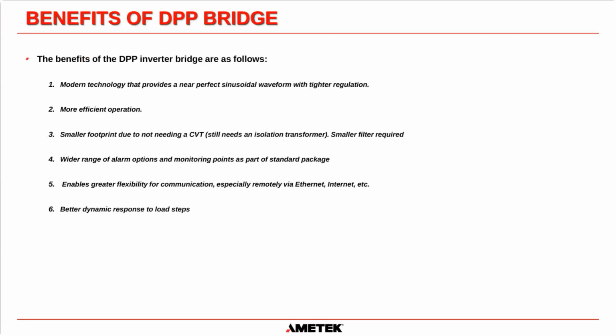One of the benefits of the DPP, the pulse width modulated inverter. Well, first of all, it's modern technology that provides a near perfect sinusoidal waveform with much tighter regulation. So the sine wave that comes out of a PWM system has extremely low THD, harmonic distortion, and when you put step loads on it, the regulation on the output waveform is extremely tight. We can really control that waveform very quickly and give you excellent regulation.